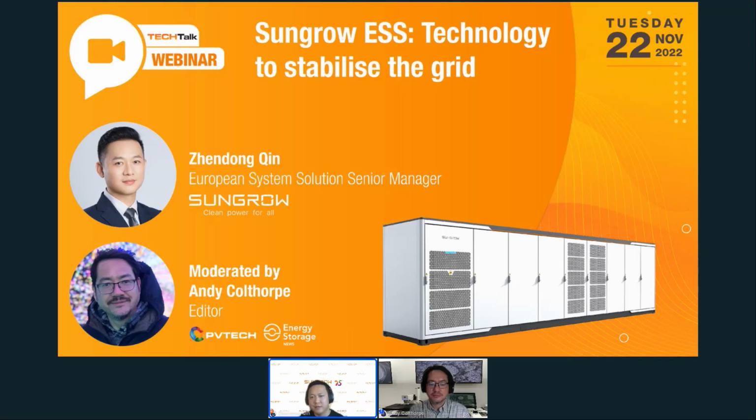I think on the designer side, the safety standard requirements of various places need to be considered, like some standards such as the NFPA series and UL 9540A. And the battery technology is lithium iron phosphate, which has a low activity and a high melting point. For the fire protection system solution, we probably need to integrate a combustible gas detector, an off-gas detector, and sensors like a temperature and smoke sensor, and an exhaust system.